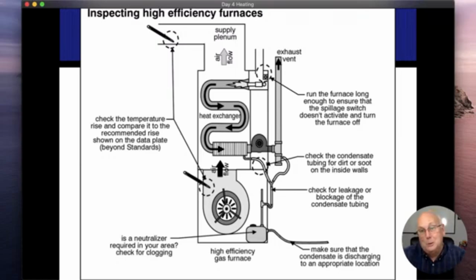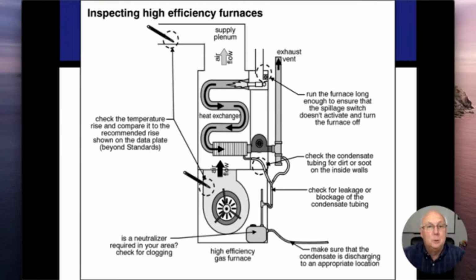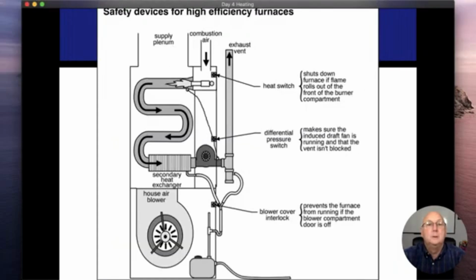Temperature rises, to me, are the most important thing that you could check. So taking that thermometer, dial thermometer, turkey thermometer, whatever, and getting that temperature rise and making sure that it matches the data plate, that's huge. All of our vents, our plastic pipes that are connected, everything should be tight and secure. I shouldn't have any stains coming out of these things. If it's orange or yellowish in any way, that usually means that something is leaking out of that pipe. They are supposed to be sealed airtight and watertight. No water, no air should escape from these.